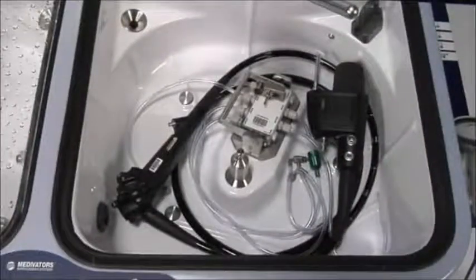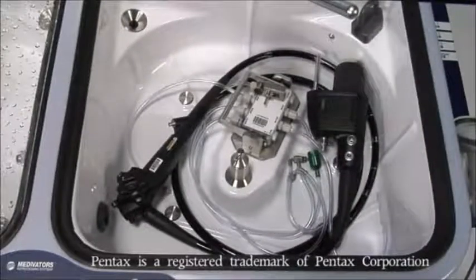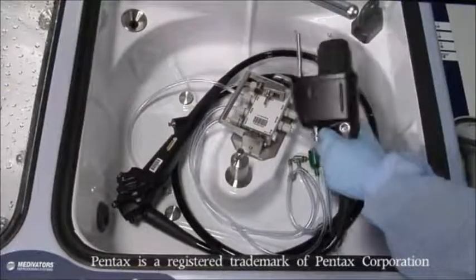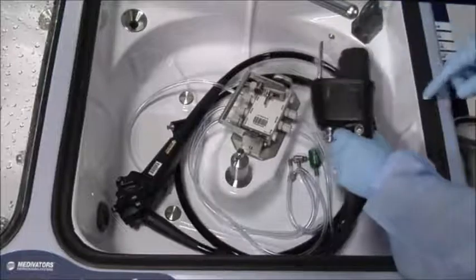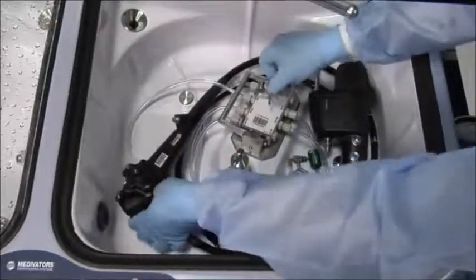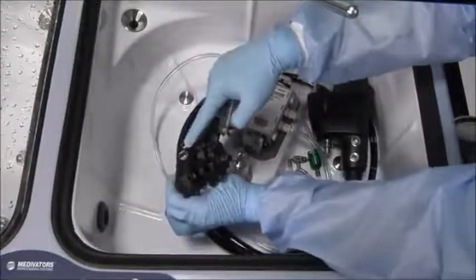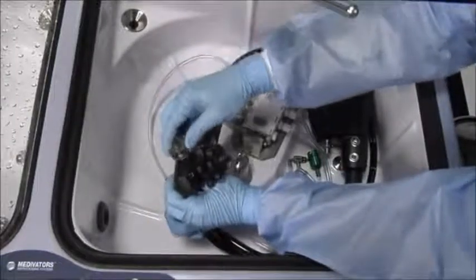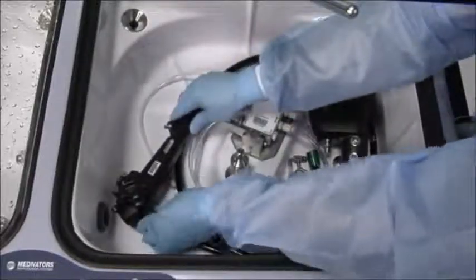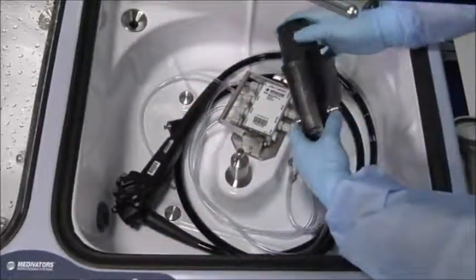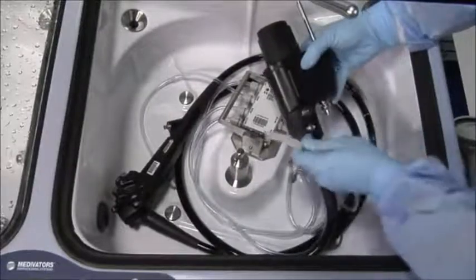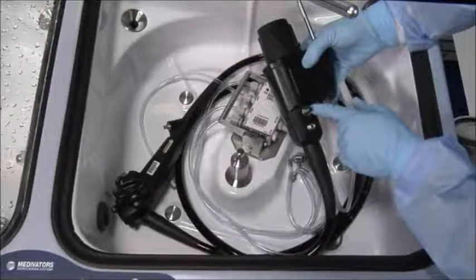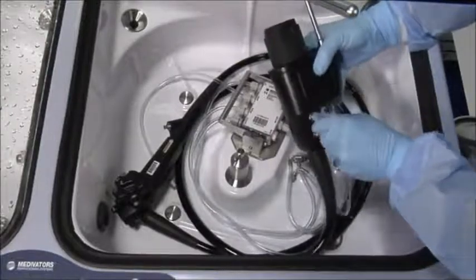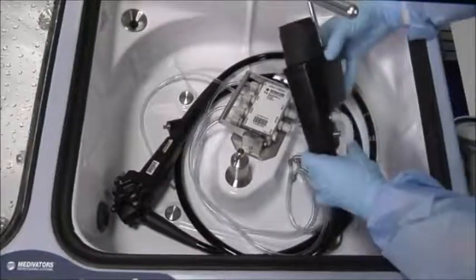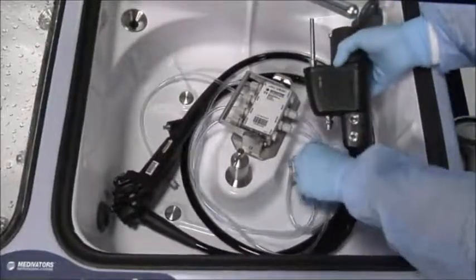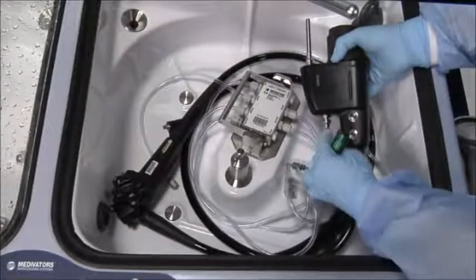We will demonstrate the connection of a Pentax 70 series endoscope to the 28534 HAN hookup with a waterproof cap already attached. Connect the channel separator to the air, water, and suction cylinders on the scope. Connect the suction connector to the suction port on the scope. Connect the leak test connector to the leak test connection on the scope.